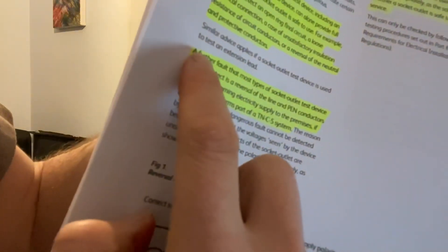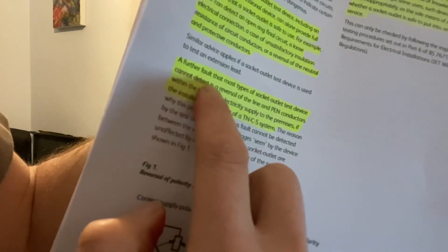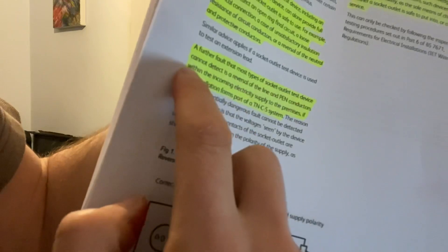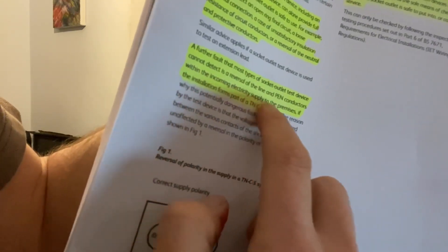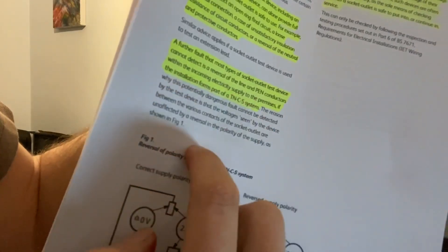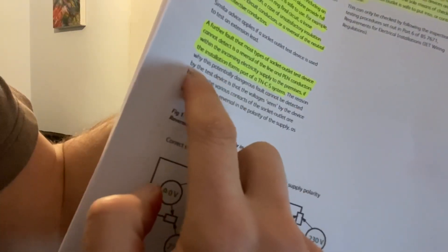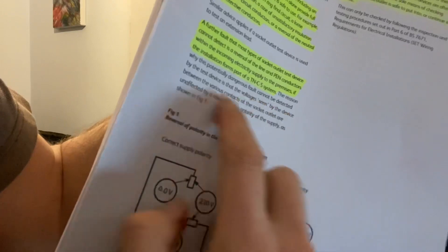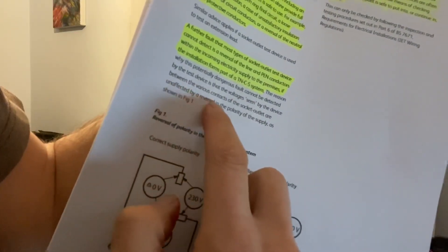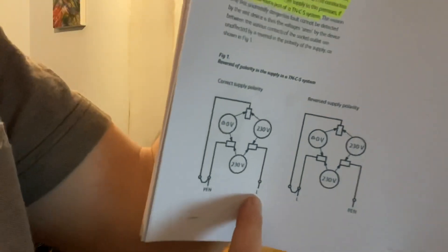It goes on to say a further fault that most types of socket outlet test device cannot detect is a reversal of the line and PEN conductors within the incoming electricity supply to the premises. If the installation forms part of a TN-CS system, this potentially dangerous fault cannot be detected because the voltage seen between the various contacts of the socket outlet is unaffected by a reversal in the polarity of the supply, as shown in the figure.